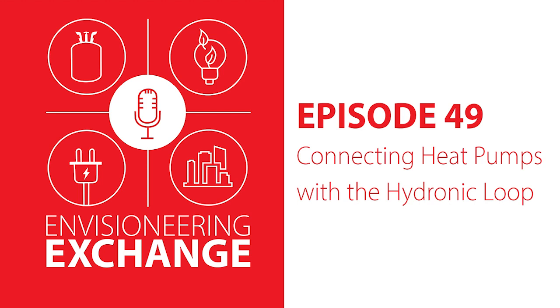Pressure controllers are good, and they definitely make balancing also easier. However, we feel that PICV is the all-in solution here, because basically a pressure independent control valve, or PICV, I think is the American terminology, is basically a pressure controller on every valve. So that is more or less the best you can get. It's the easiest to balance. There's also no way to make mistakes. And it's also very good at controlling and very precisely controlling things.